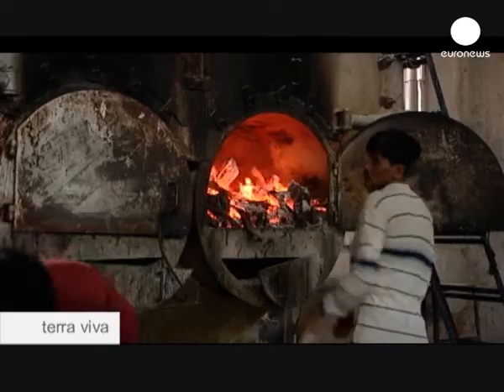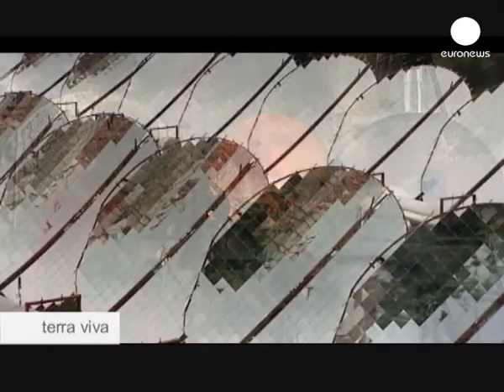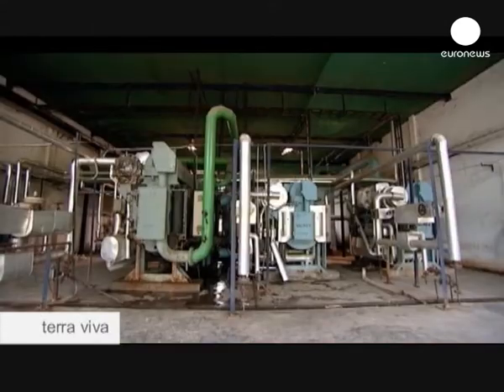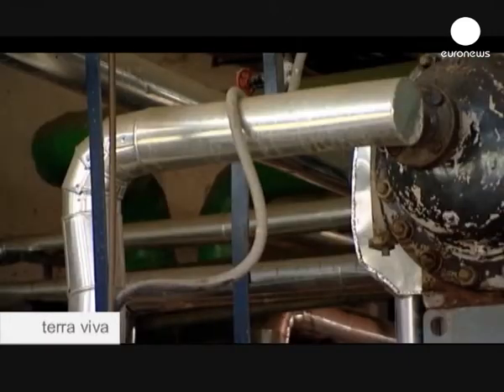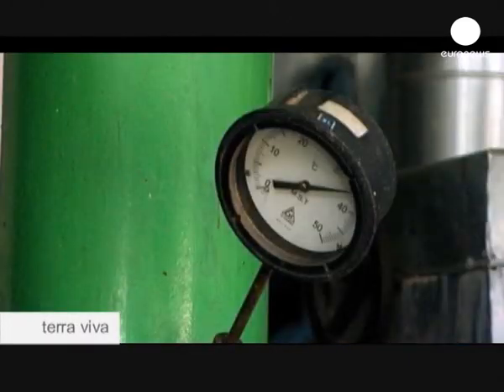Harnessing the sun means saving 1,000 kilos of wood every day. In total there are 1,250 square meters of reflectors, and the light is reflected onto a heat exchanger to generate steam, which is sent to our air conditioning plant. We are doing 100 tons, which is about 350 kilowatts of air conditioning for our hospital.